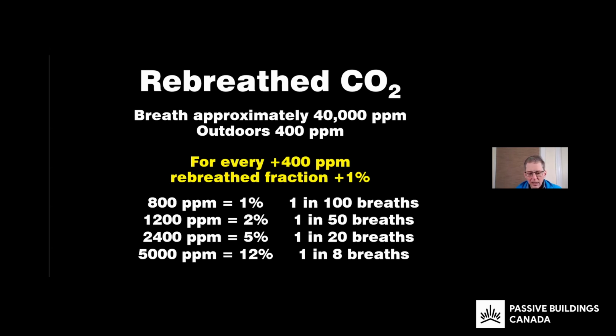That day that my daughter's classroom had it, when she caught her cold with symptoms within 48 hours afterwards, was 5% rebreathed air. And 5,000 parts per million is the occupational health and safety limit for 8 hours of exposure. That works out to 12%, and 1 in every 8 breaths is basically like you're breathing in everyone else's air.